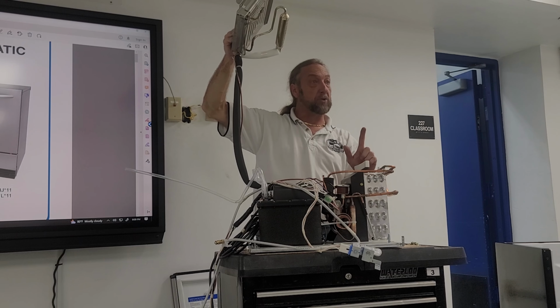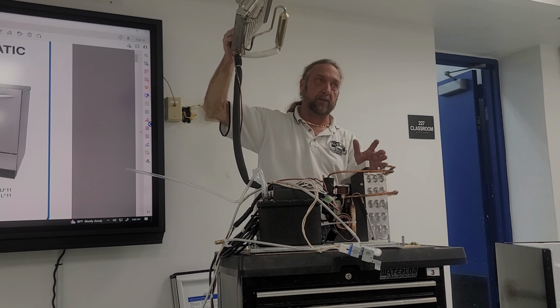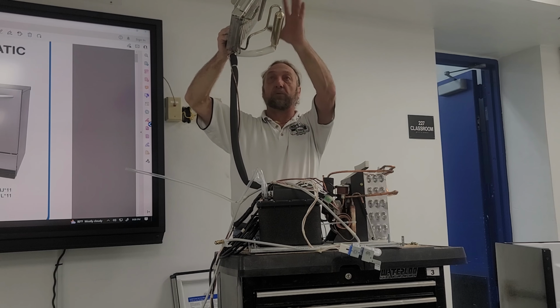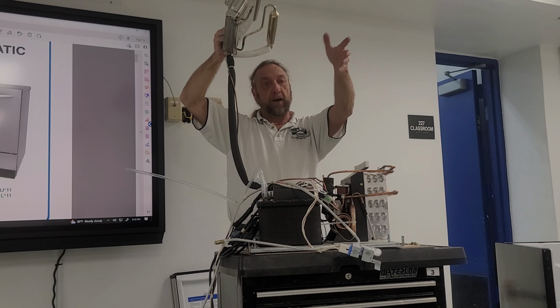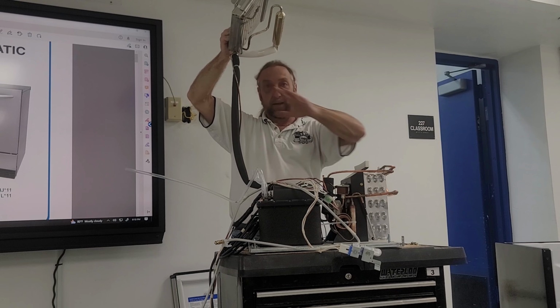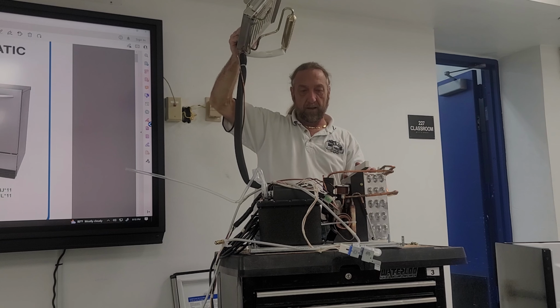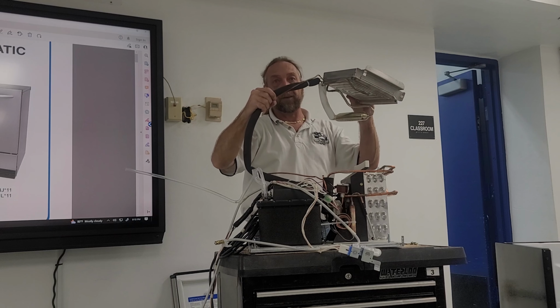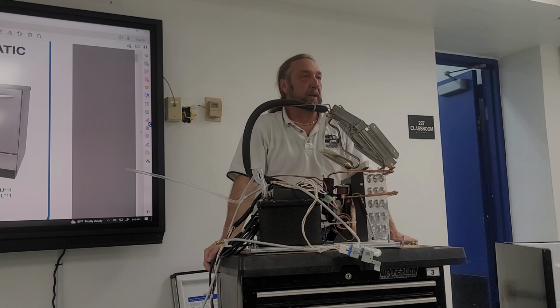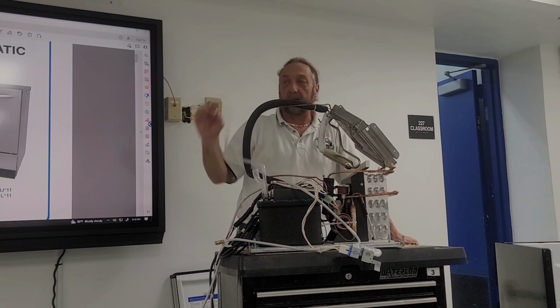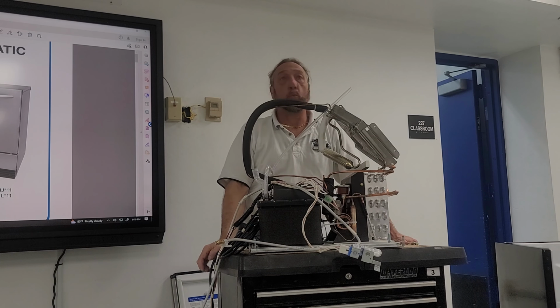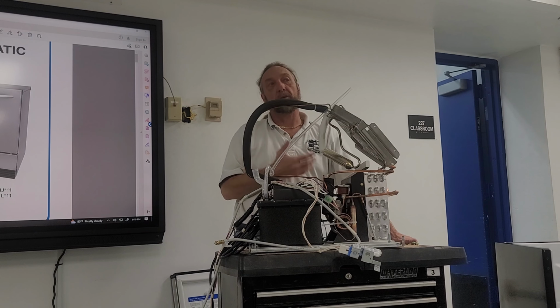Okay, the only time we use a capillary tube is when we're refrigerating, producing ice. So that will come up here and refrigerant will flow through here normally. When we go to remove ice, the hot gas valve just goes straight up here. The ice slides off and produces ice. So that's about it. Is there any questions about any of these components or anything about the service of it? No, good. No? I think it's the ice that it makes. The ice is approximately 1/4 inch to about 3/8 of an inch thick. About that big. Okay, they're decent size ice. They're not real big. Remember, this machine only runs for about 20 to 25 minutes on average.